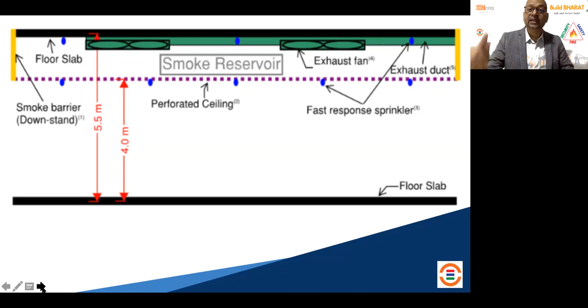But the moment you have perforation which is more than 25%, the smoke is going to go out anyway. Then you need to manage the smoke even in ceiling void areas. You can't just keep it there unprotected. You have to provide the sprinkler there, you have to provide a detector there, you have to have an exhaust fan there, and that's how you manage the smoke.